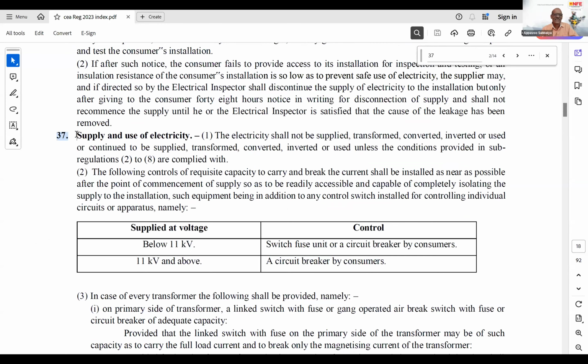Sir, this regulation, which has come up in June 2023, states that the consumers who are below 11 kV, that is like 3.3 and 6.6 kV consumers, are permitted to use a switch fuse unit or a circuit breaker at the point of supply. And they have given a condition wherein the transformer is above 1000 kVA. For these consumers, a breaker is mandatory.